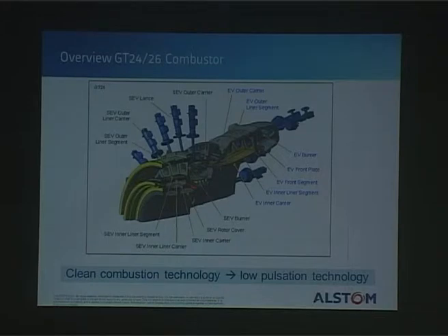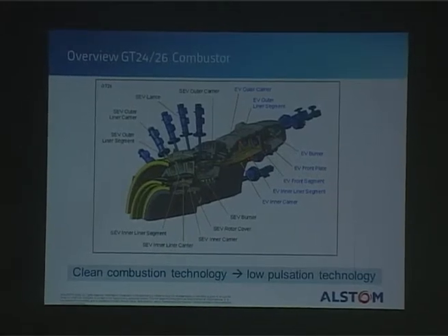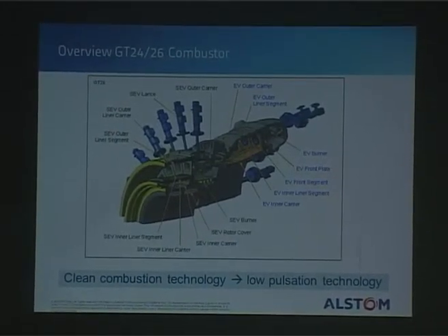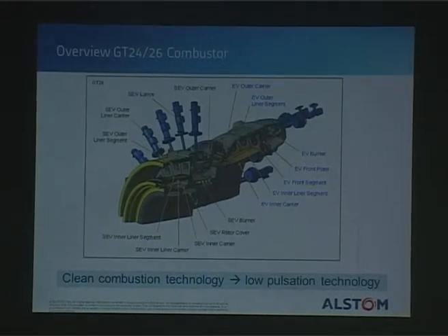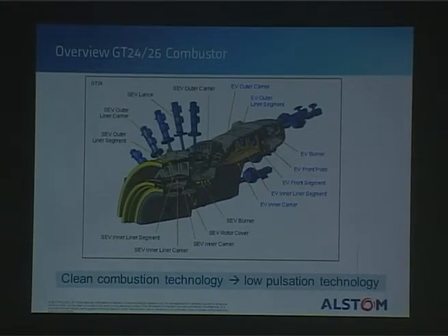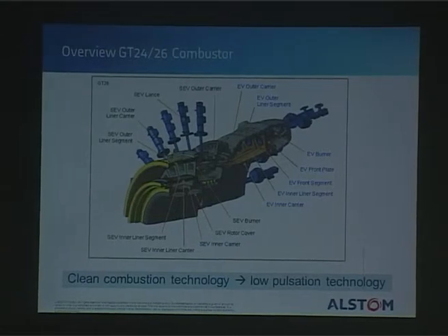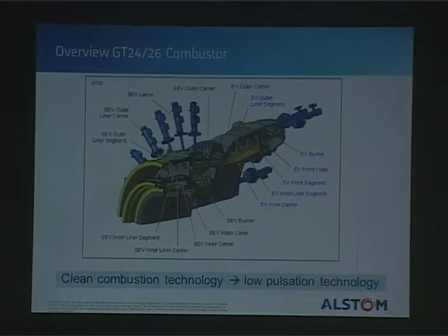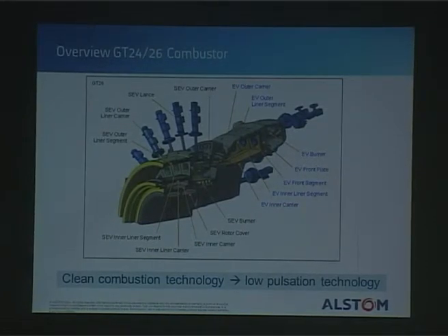What I'm talking about today will be about this first combustion chamber and what kind of models we use to predict the thermoacoustics in that combustion chamber. Of course, our customers at the end don't care too much about thermoacoustics. We care, but it's mostly because we want to achieve lifetime, and that's also what the customer wants to have. And to achieve lifetime, you don't want too high pulsation levels because that reduces your lifetime.